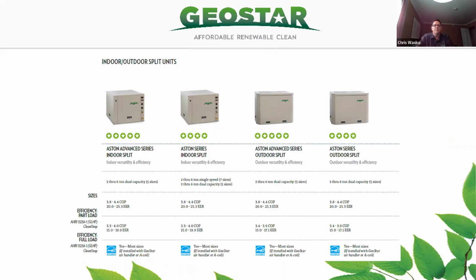So you have the Aston indoor split, which is the 2 through 6 ton, available in single capacity and dual capacity. The Aston Advanced series to the right of that, which is the third unit to the right, Aston Advanced series outdoor split. These are 2 through 6 ton dual capacity units. These have the option to have the flow centers and the pumps put into the unit on the outside. So you'll have the convenience of having everything all in one place when you're working on it. These units are used in applications where you just don't have quite enough room on the inside to install a unit, or have access for an area where you can put the utilities in there. So you're able to put this on the outside of the home in a split application, being able to use it with an air handler in an attic space or wherever you may choose.